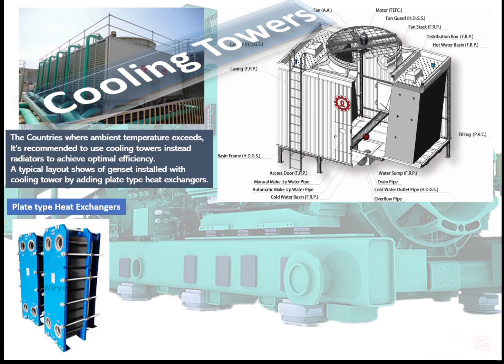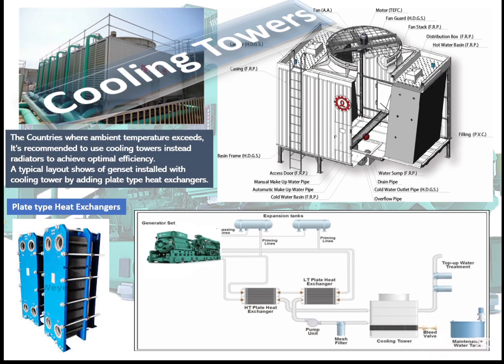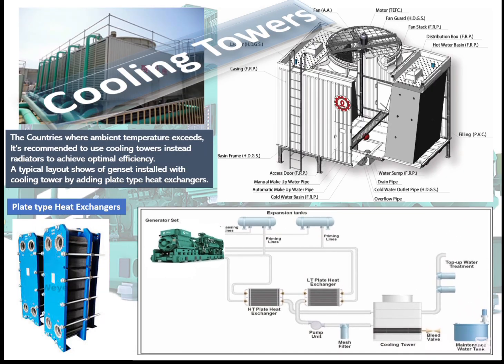The additional items we install with a cooling tower are the plate type heat exchanger and circulation pumps that can throw the water back to the cooling tower, because the cooling tower is located at a height. This is a typical layout, a typical picture of a Cummins genset installed with a cooling tower. We have the genset, a heat exchanger for LT and HT, then we have the pump, we have the cooling tower, and we have the LT and HT expansion tanks.